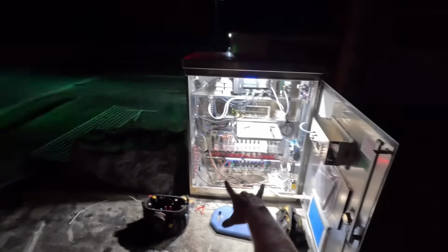This is green, so what it's gonna do now, and guys, I'm excited, so I'm telling y'all some stuff. But what it's gonna do now is that and this mimic each other, just like we didn't do absolutely anything. You can even tell on the load switches what it's doing. But the moment that this railroad is activated, this one will go green, this one will go red, and this section will clear out the intersection. They'll get held back there, and then after 8 seconds, enough time for these guys to clear out, hopefully. Should be.